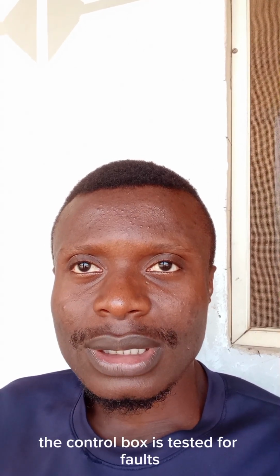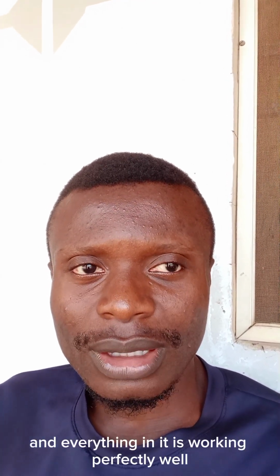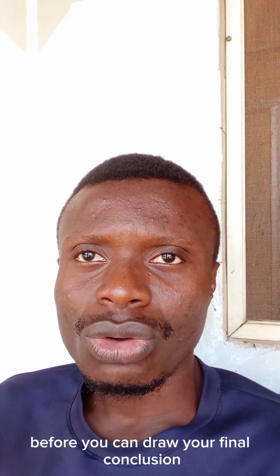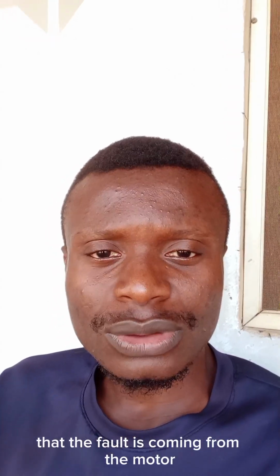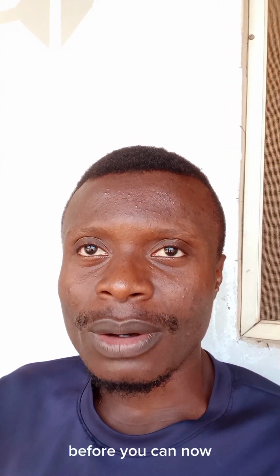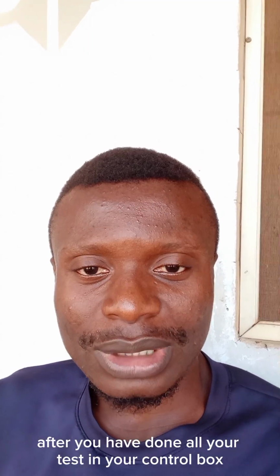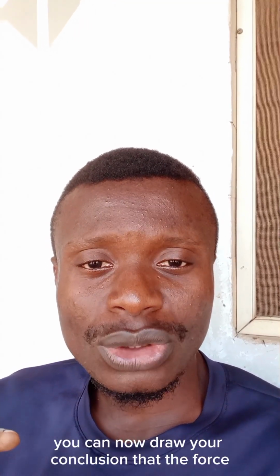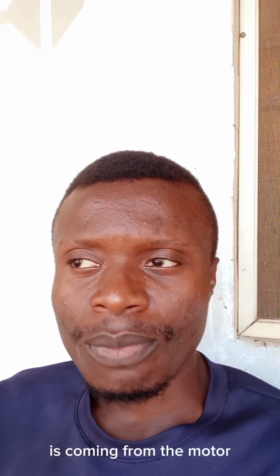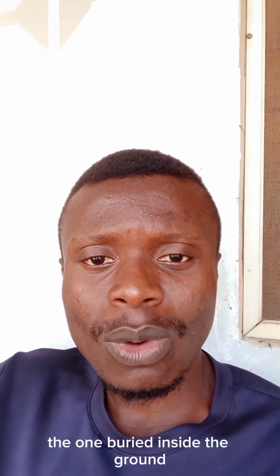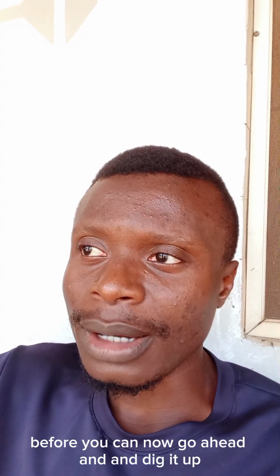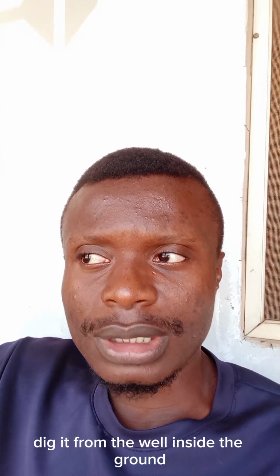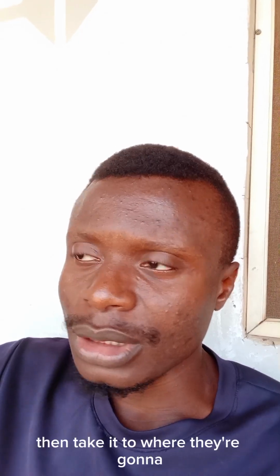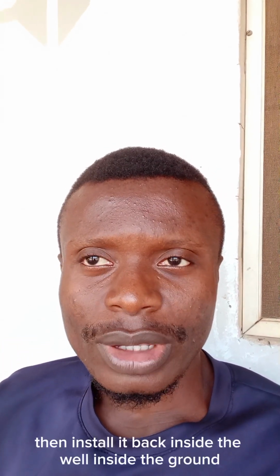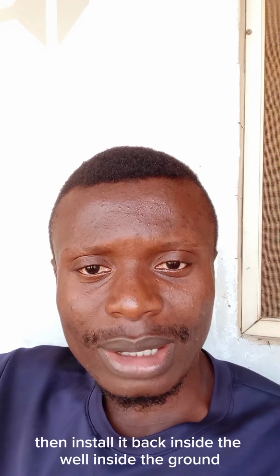So you make sure that the control box is tested for faults and everything in it is working perfectly well before you draw your final conclusion that the fault is coming from the motor. After you have done all your tests in your control box and discover that there's no fault there, you can now conclude that the fault is coming from the motor inside the submersible pump, the one buried inside the ground. Before you go ahead and dig it out of the well, after digging it up, you take it to where they're going to fix the motor, then install it back inside the well, inside the ground.